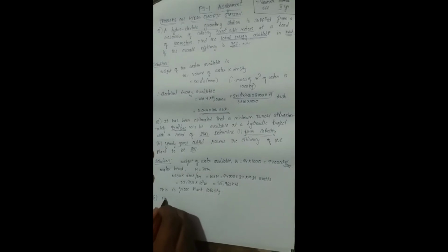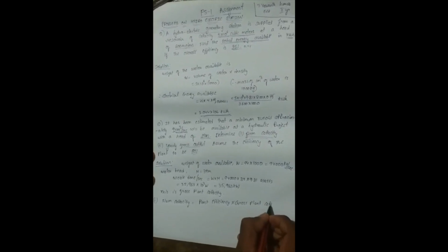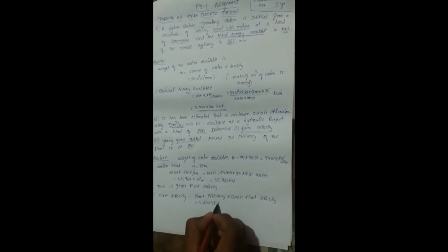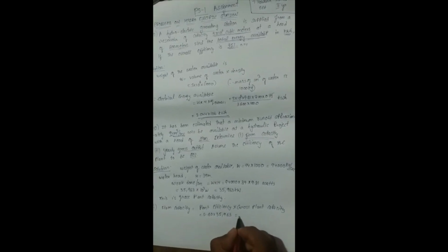This is the gross plant capacity. And the firm capacity is equal to plant efficiency into gross plant capacity, which is equal to 0.80 into 35,963, which is equal to 28,770 kilowatt.